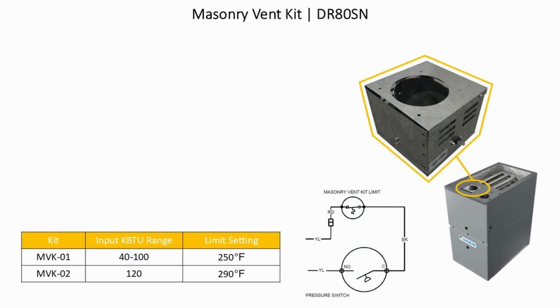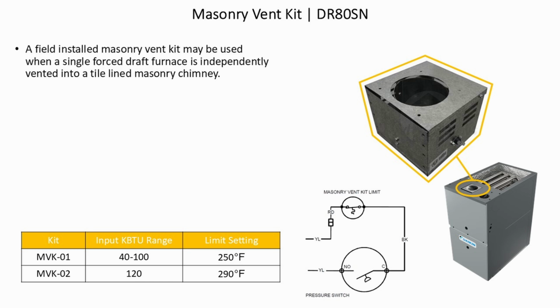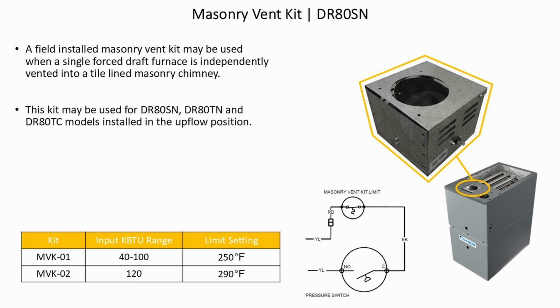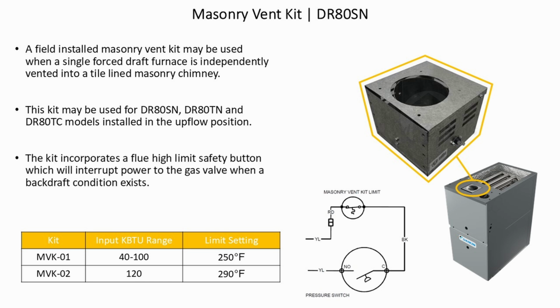Masonry vent kit for the DR80SN. A field-installed masonry vent kit may be used when a single forced draft furnace is independently vented into a tile-lined masonry chimney. This kit may be used for DR80SN, DR80TN, and DR80TC models installed in an upflow position. The kit incorporates a flue high-limit safety button, which will interrupt power to the gas valve when a backdraft condition exists.